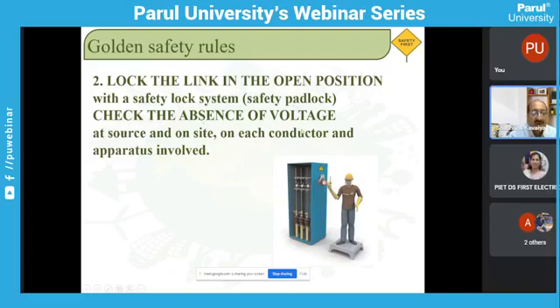Check the absence of voltage at source on site on each conductor and apparatus involved. Once it is isolated, we have to check whether there is a power voltage there. With a live line detector you can check from a bit of a distance. You keep the live line detector here, and it will tell you there is power or no power. You don't have to touch and see, because if there is power, you will get shocked.